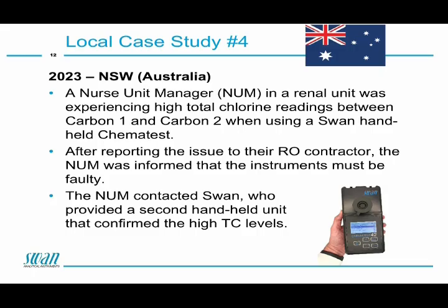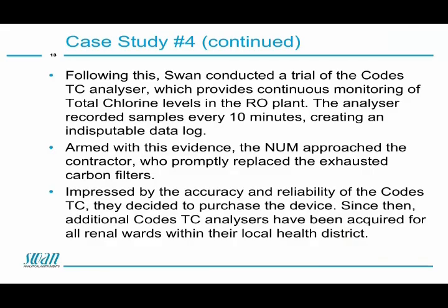Following this, we decided to conduct a trial of the CODES TC analyzer, which is the continuous monitoring analyzer that is on my banner outside there. It provides continuous monitoring of total chlorine levels, and the analyzer recorded samples every 10 minutes, creating an indisputable data log that the levels were high.